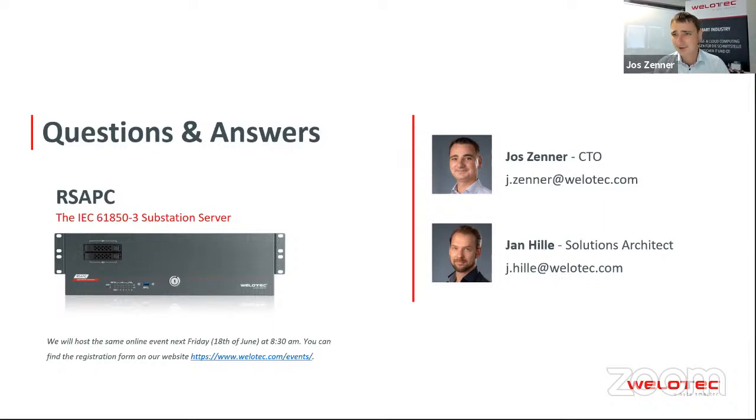There is an AC power supply that is covering all the AC range from 90 to 260 volt AC. Then we have a DC power supply, which is covering from 16 volt DC up to 160 volt DC. So this will meet your 110 volt DC.